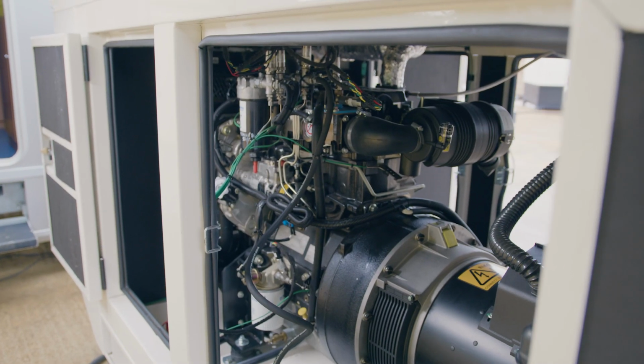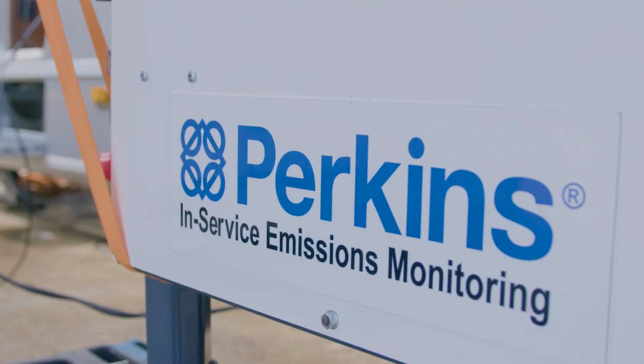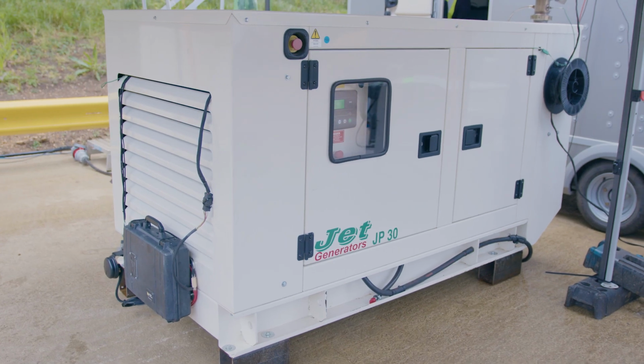So today we've been looking at the genset we've had on test here at Perkins. The genset's been running on HVO, hydrotreated vegetable oil. It's a drop-in fuel that can be used to replace diesel. We've been doing some testing to see what the effect is on the genset, whether there are any changes needed in maintenance, and what happens to the emissions during the running of the genset itself.